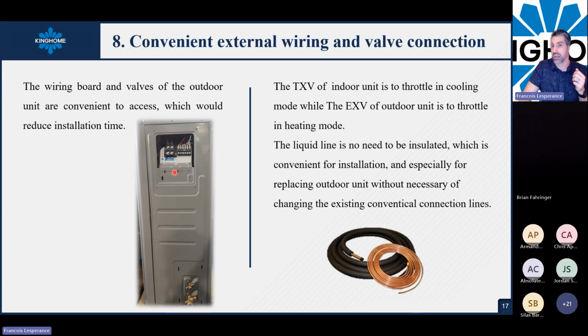So this is what it looks like inside of it. You will have this access here for your high voltage and low voltage connection, and all the piping connections are outside the cabinet. So this is why I said it's more a plug and play unit, because you don't have to remove any panel, you don't have to adjust anything. It's already built in, it's ready to use. So you just have to plug your high power, plug your 24-volt connection, make your piping, as we said, perfectly fine. Your pressure test is good, your vacuum is good, and then you're good to go.